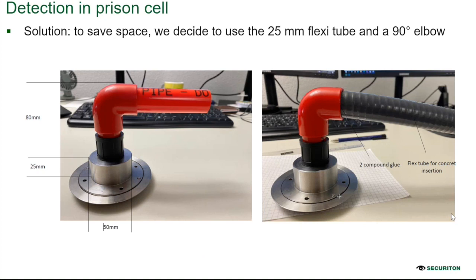Is it necessary to go inside the cell to do ordinary maintenance on the ASD system? No, not for ordinary maintenance. It is not necessary because it is possible to perform both pipe cleaning and fire testing from the outside using a test sampling hole on the pipe.